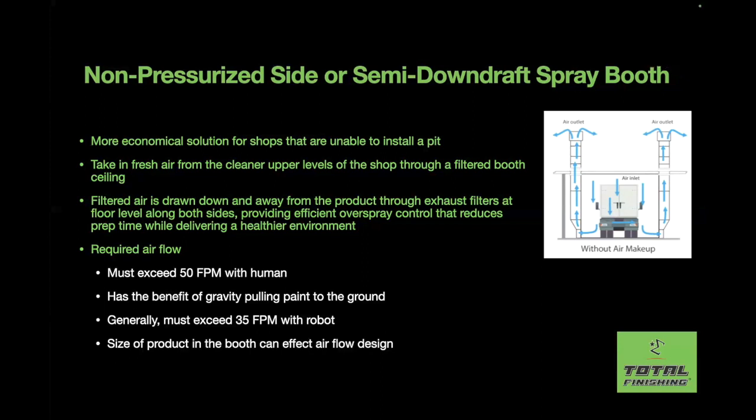Well, isn't there a device, I forget the name of it, but it's a differential measurement that automatically detects when the filters need to be changed, because it has a sensor on the face and then a sensor in the plenum. Yep. There is just what's called a manometer, which is a requirement of every spray booth to have.